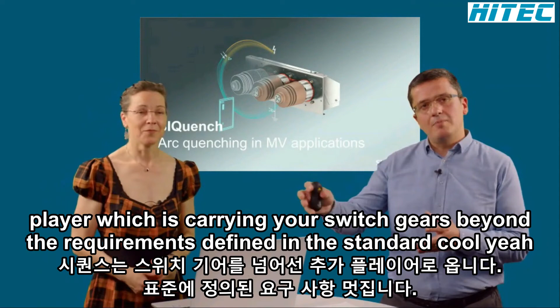First, your switchgear design should fulfill the internal arc classification as per IEC, with defined durations of 0.1 second, 0.5 second, or 1 second. Then SIQuench comes as an additional player, carrying your switchgear beyond the requirements defined in the standard.